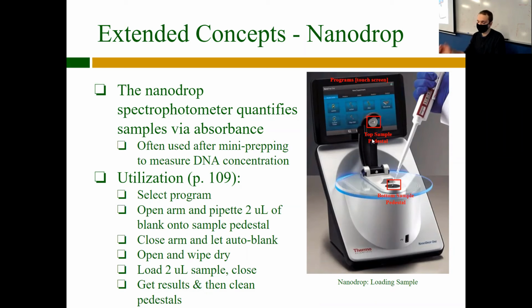After you put your blank onto it, you get this arm, you close it, it will auto blank. That's something new that this unit has. We used to have to blank it manually, but they learned from that, I guess, and they added an auto blank feature. So you just close the sample pedestal. It will do the blanking. That will take a few seconds, maybe 10 to 15. Then you'll open up the arm. You'll get your wipes. You'll wipe off to make sure it's clean.